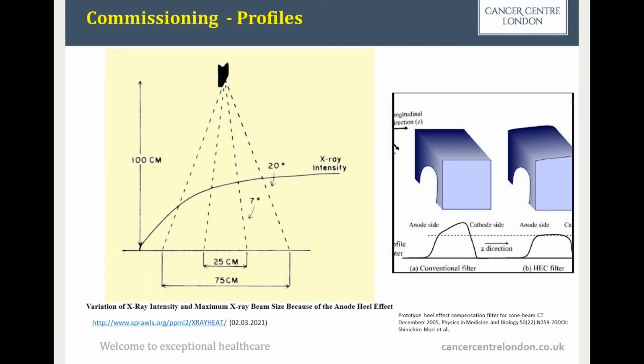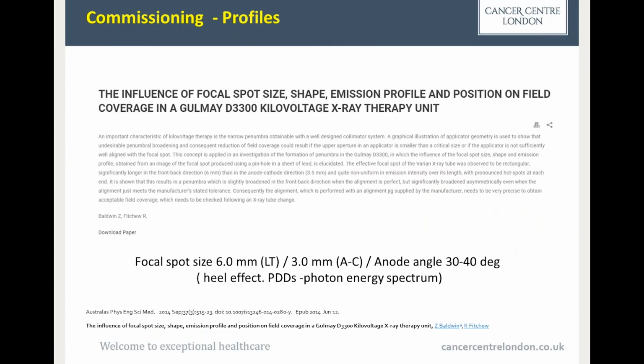And it is again the next slide which shows how this heel effect can work. This example is for radiology and is most visible in mammography. But if we go to our results, how we measured our profiles, firstly, I confirmed what the anode angle is. Anode angle for diagnostic is about 20, 16 degrees, 15, something like that. And focal spot size is about 1 millimeter, 2 millimeters, 3 millimeters max. Even for mammography it is 0.1 millimeter.